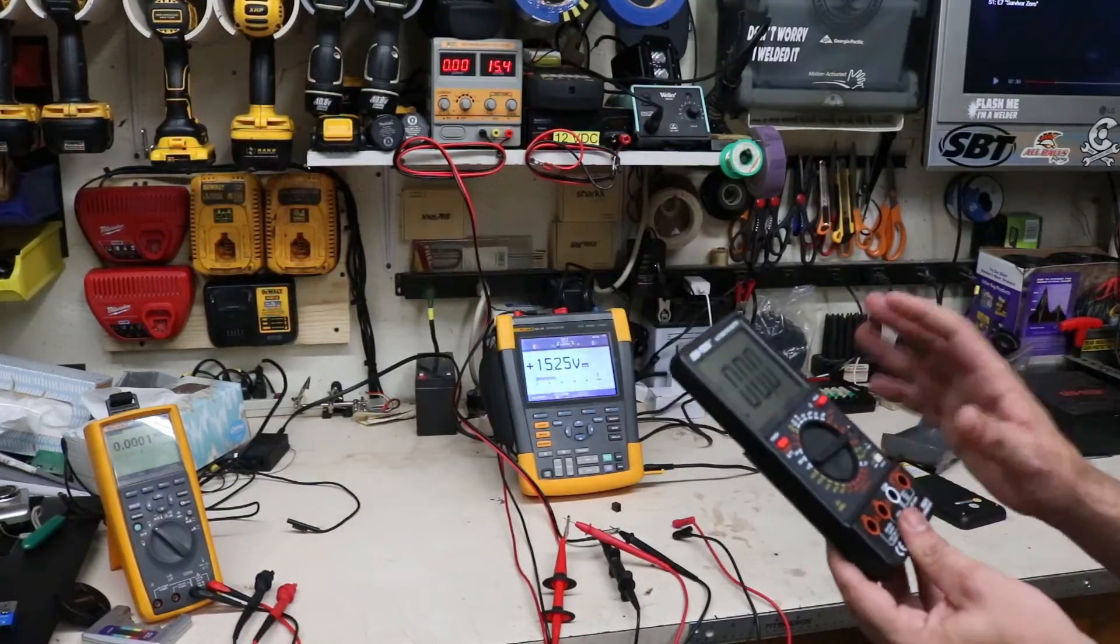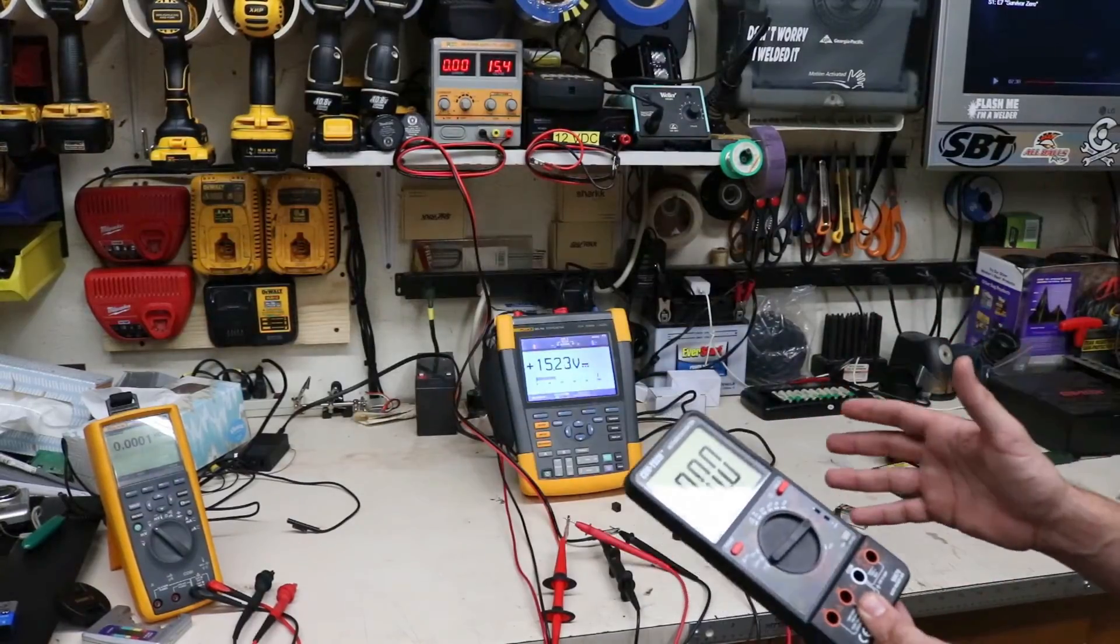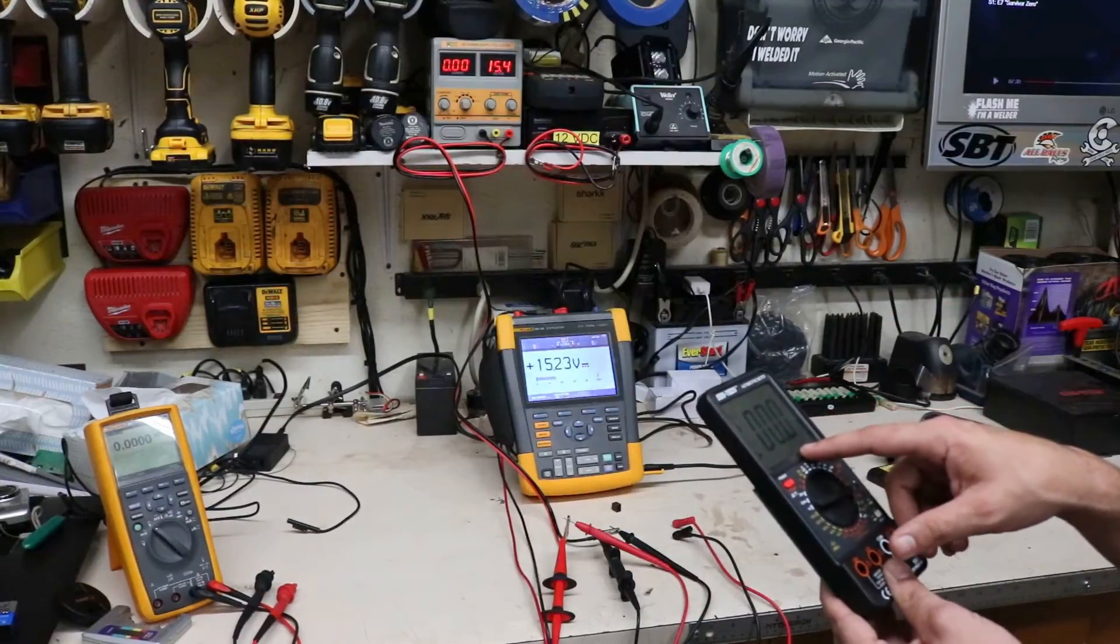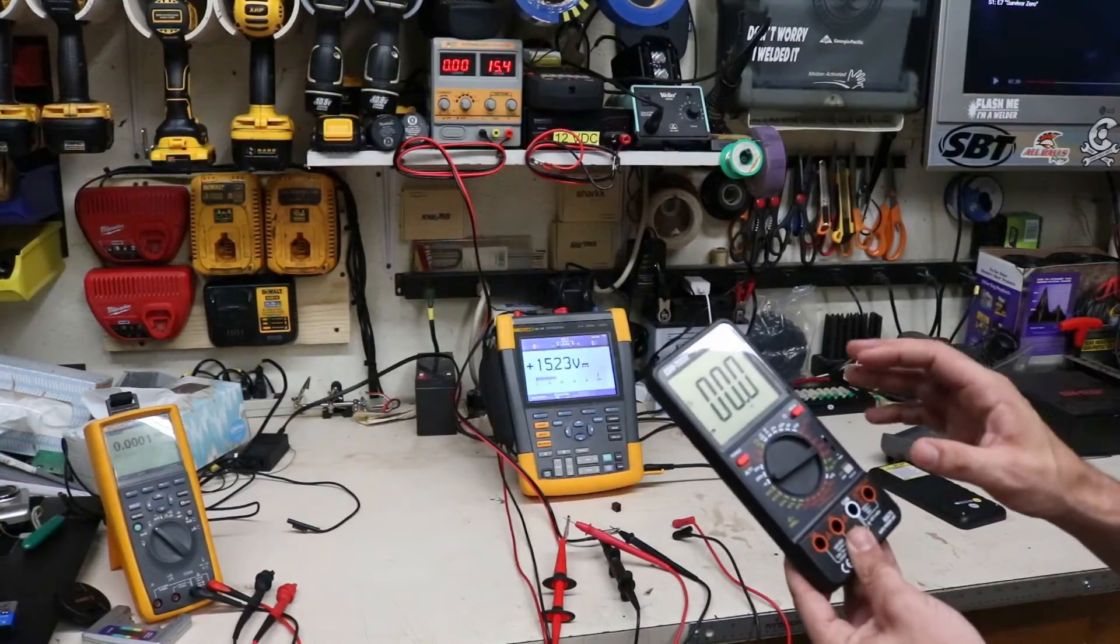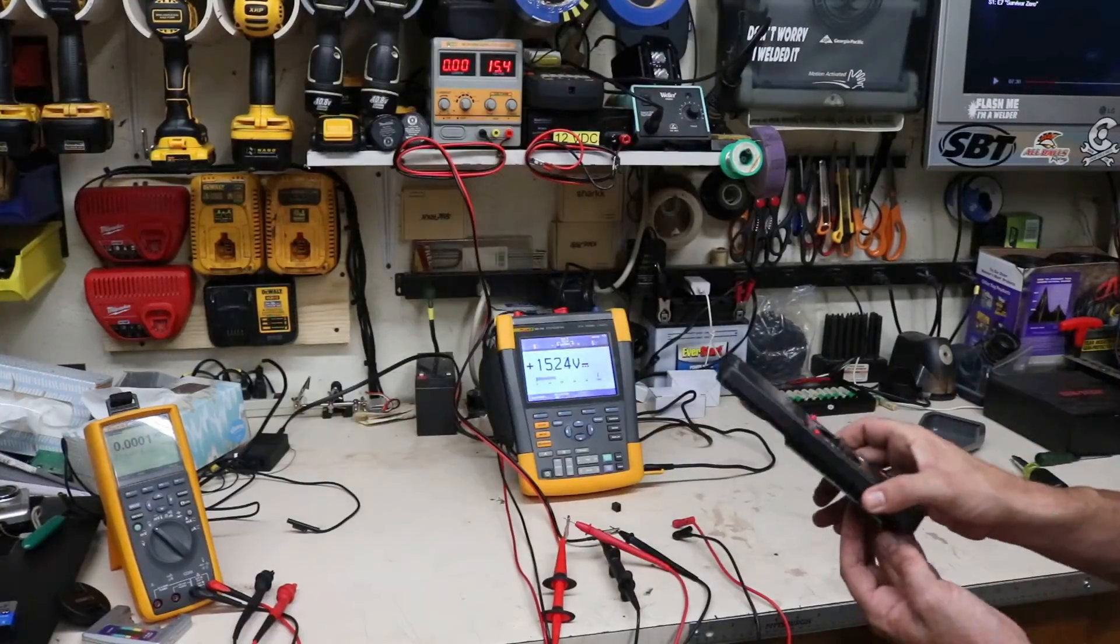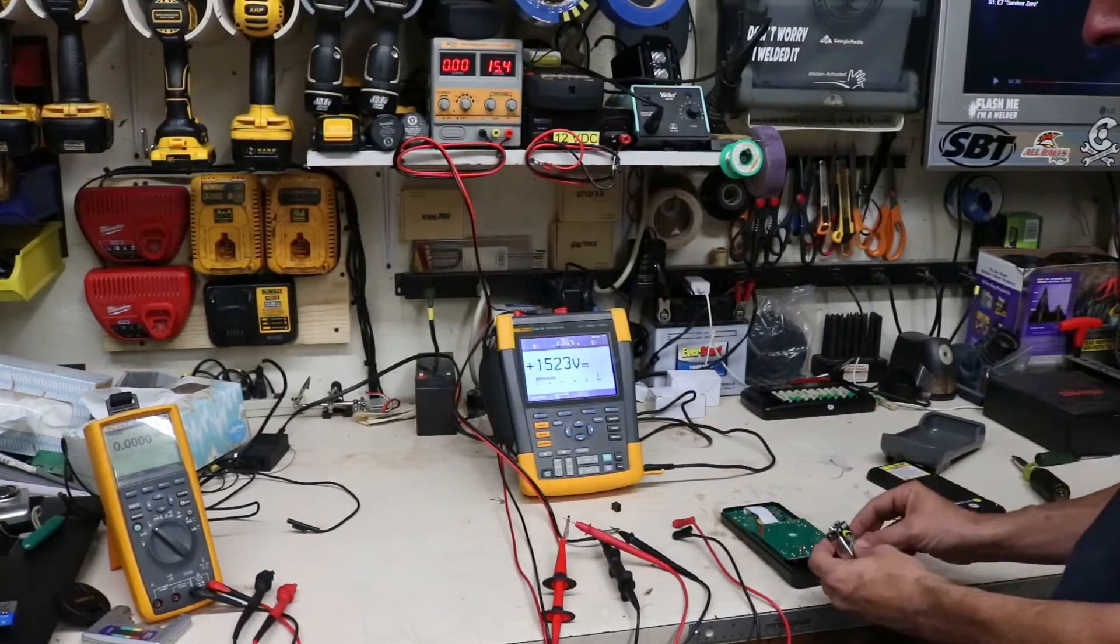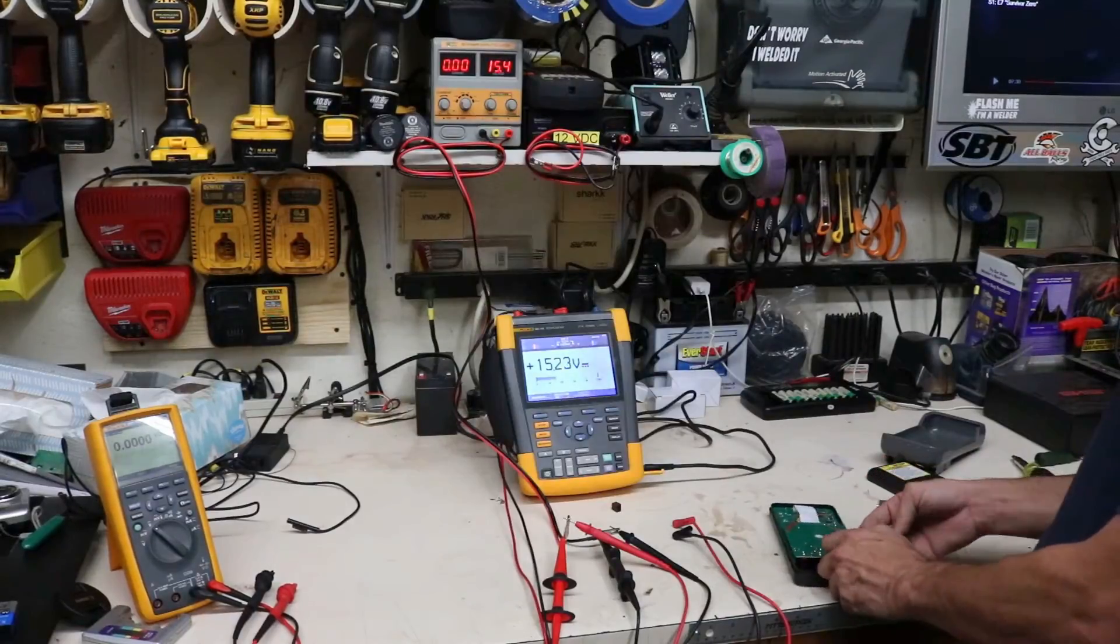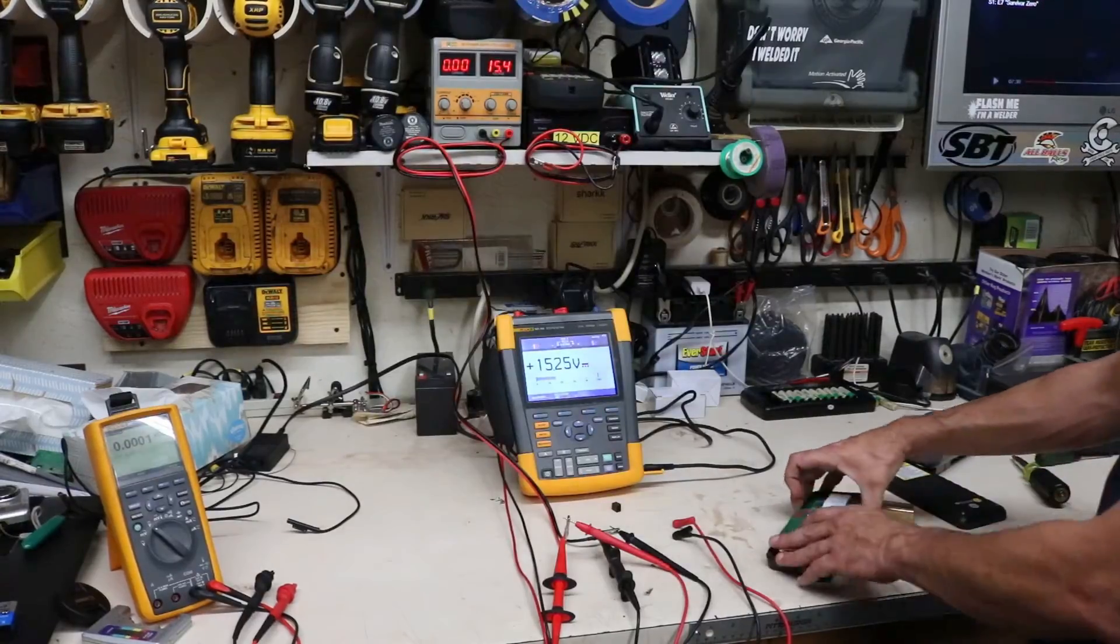So the first thing you want to check with any multimeter, doesn't matter if it's a cheap $20 meter, $100 meter, or a $1,000 meter, is to check the batteries. This one does have a battery indicator on it, and it shows up here in the corner. So the battery is getting low. And as we've seen, we had up to about a 5.5 or 6 volt difference. So the first thing you want to do before you start adjusting it is to put a new battery in it, just to see if that makes any difference in the reading. Because as the batteries start to die in all test equipment, your readings can start to deviate pretty far from what they should be.